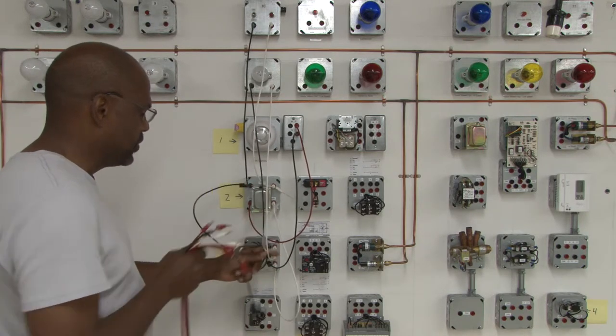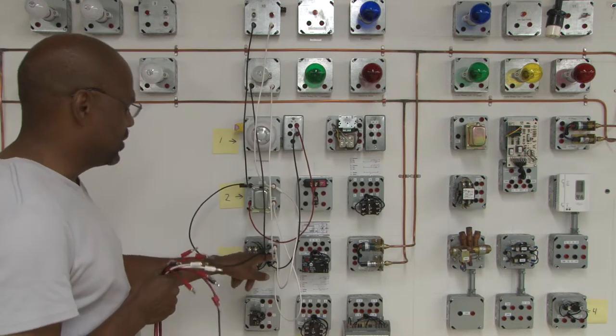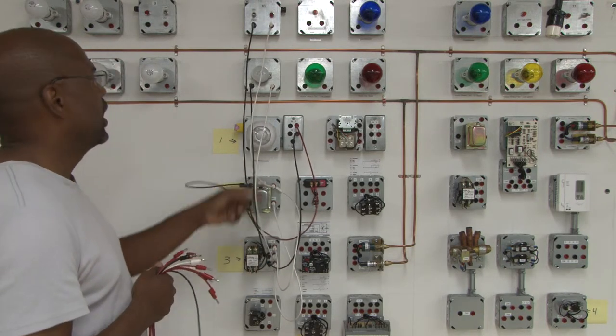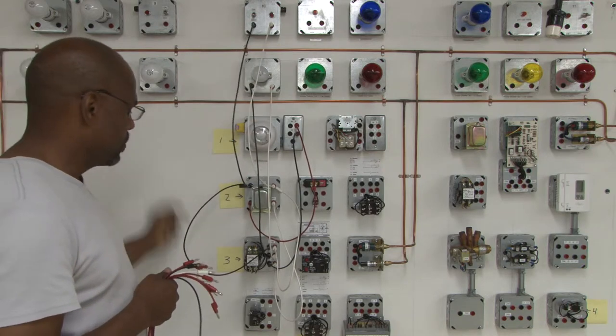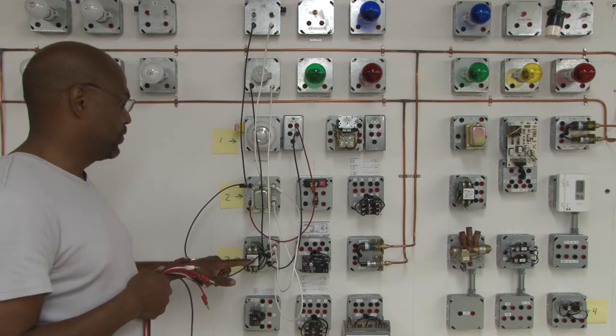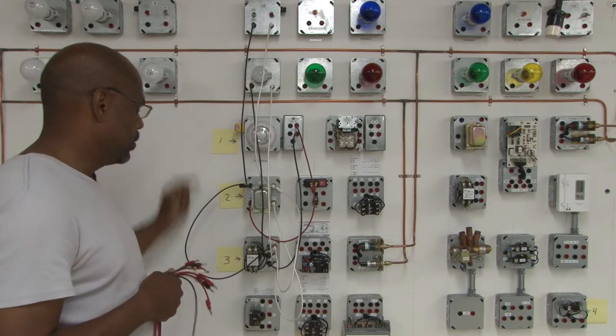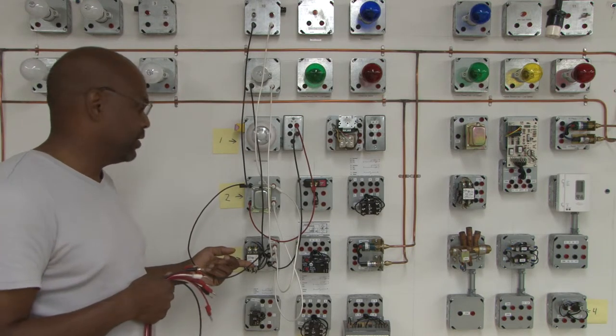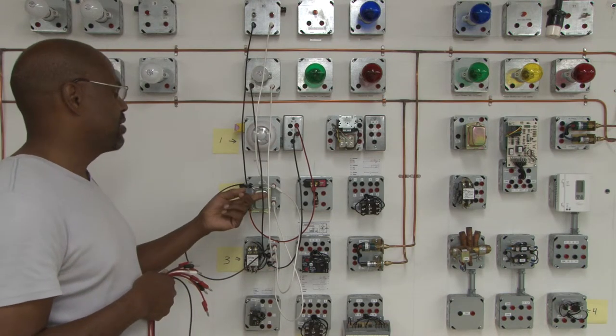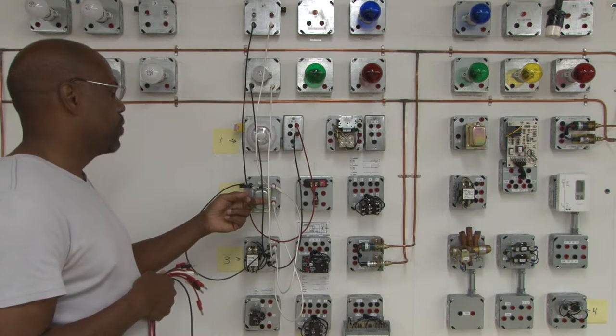Now the switching is done by the contactor and this is the outlet terminals of the contactor T1 and T2 and it goes straight to the load. So when this contactor becomes energized it will send power to the load. And the only way to energize the contactor is by having control voltage at the coil which is coming from the transformer.